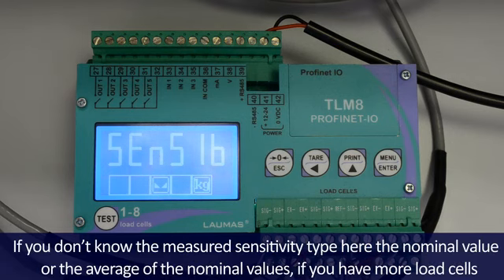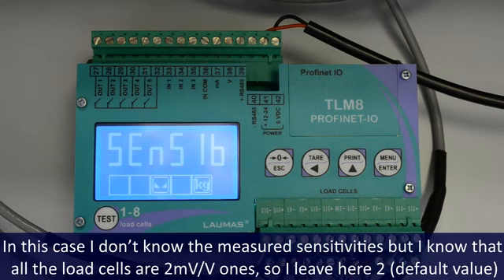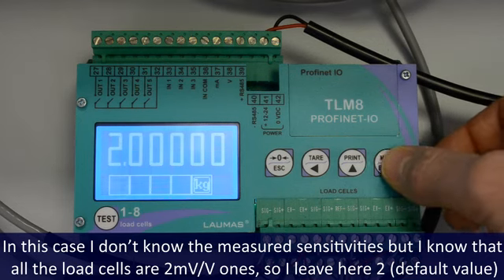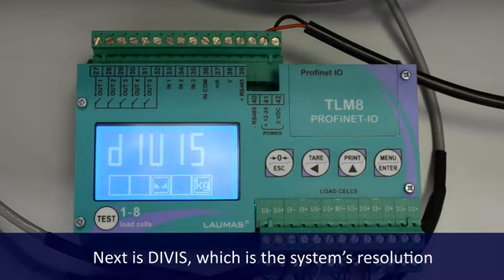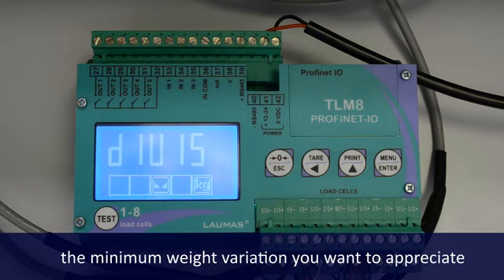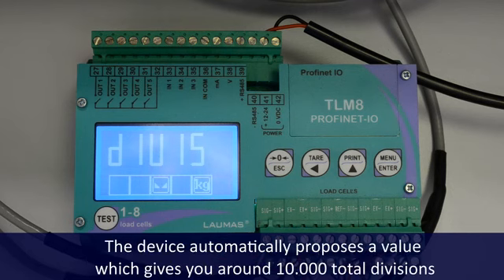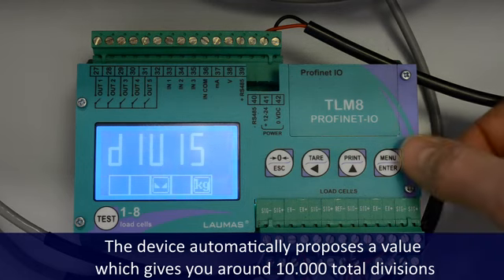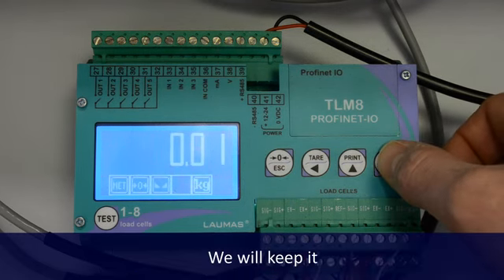If you don't know the measured sensitivity, type here the nominal value, or the average of the nominal values if you have more than one load cell. In this case, I don't know the measured sensitivities, but I know that all the load cells are 2 mV over volt ones, so I will leave here 2, the default value. Next is DIVIS, which is the system's resolution, the minimum weight variation you want to appreciate. The device automatically proposes a value which gives you around 10,000 total divisions. We will keep it.